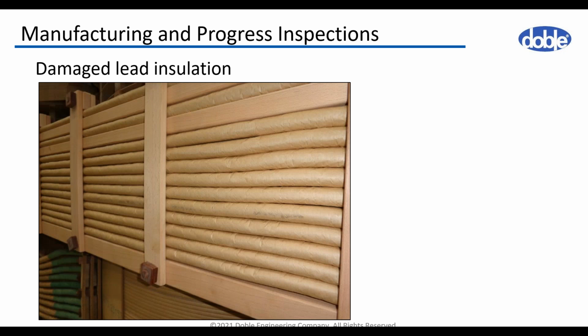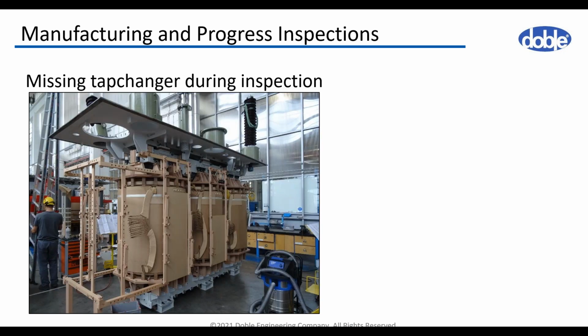On that picture, we have some damages on the tap lead insulation, which is another issue, and it's something we don't like to see on a new transformer, and it can cause a problem during service, during testing as well. And what we can check also is the manufacturing progress. In that picture, we have the transformer ready for inspection, but with the tap changer missing. In this situation in particular, we have a delay of a few days or few weeks practically, because the manufacturer had a problem with the supply of the tap changer.